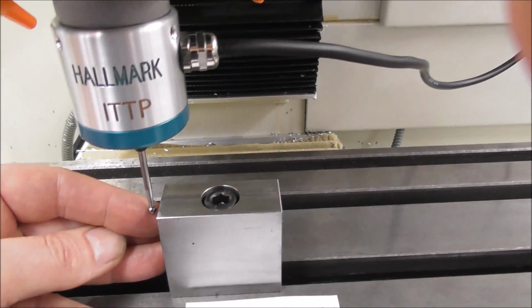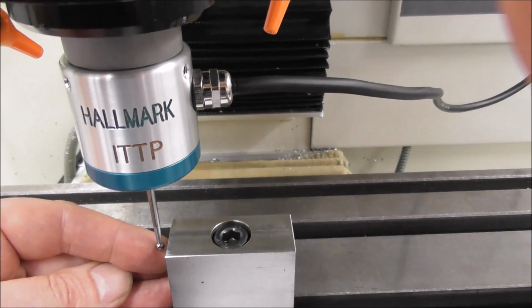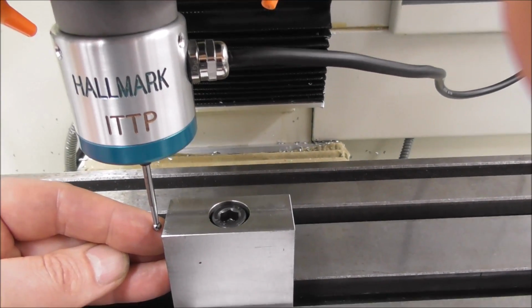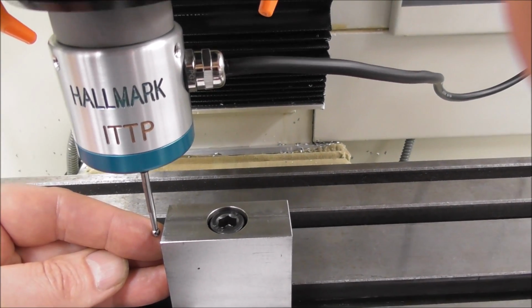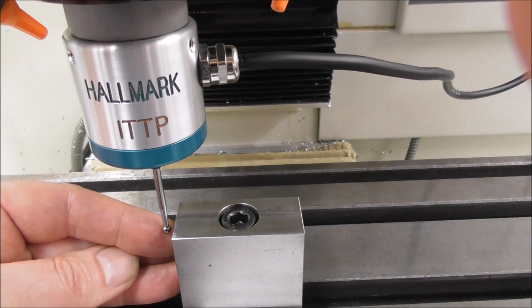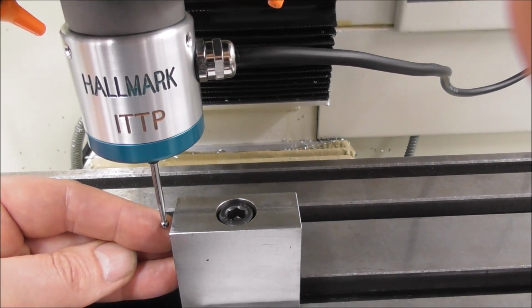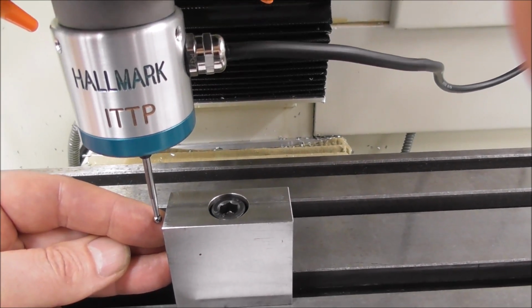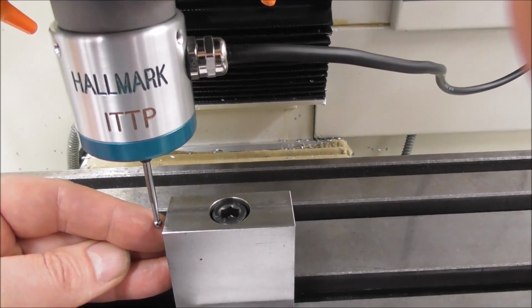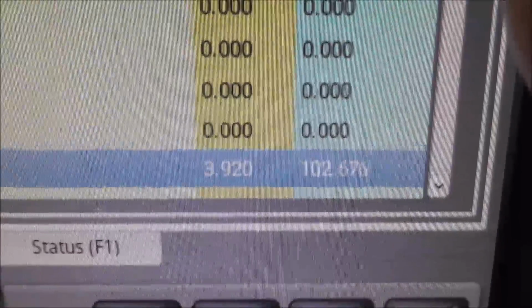So whatever diameter your tip is, if it's 5/32, you measure it with a micrometer and you subtract 2.4 thou on the diameter, 2 thou and 4/10, and you will get a pretty accurate average pre-travel to enter in. And if you're in metric, you'll be doing that in metric. If you're in inches, you'll be doing that in inches.